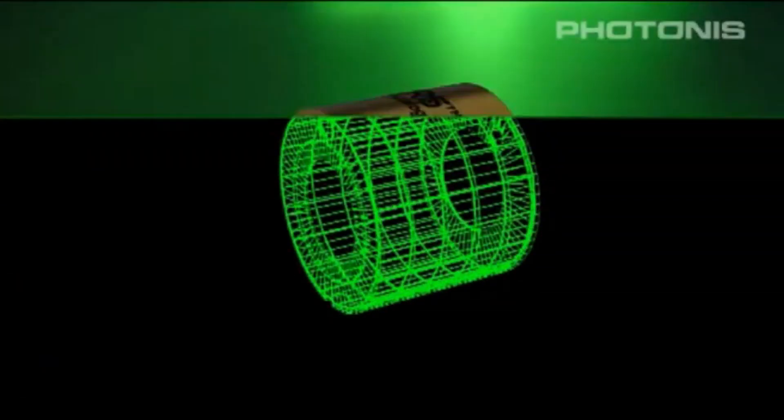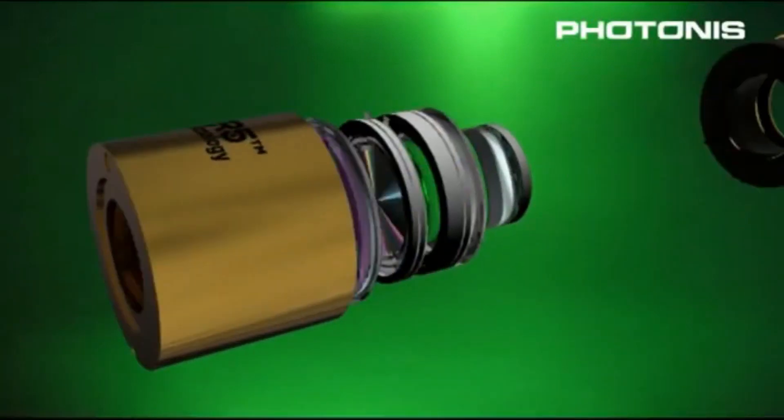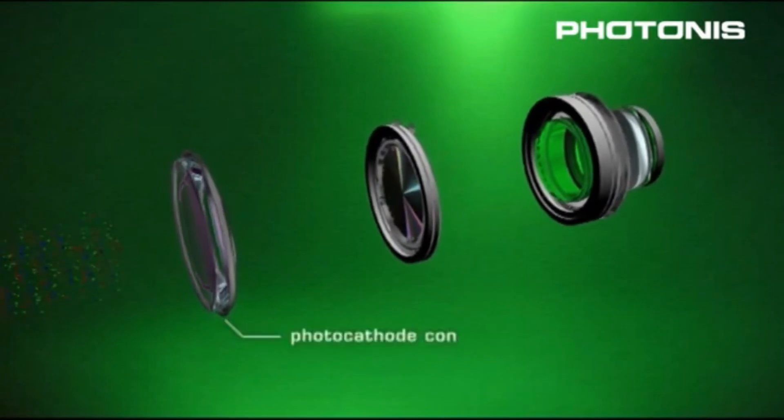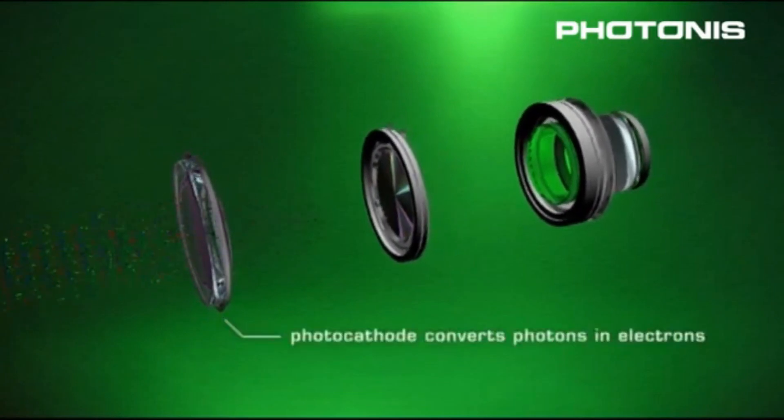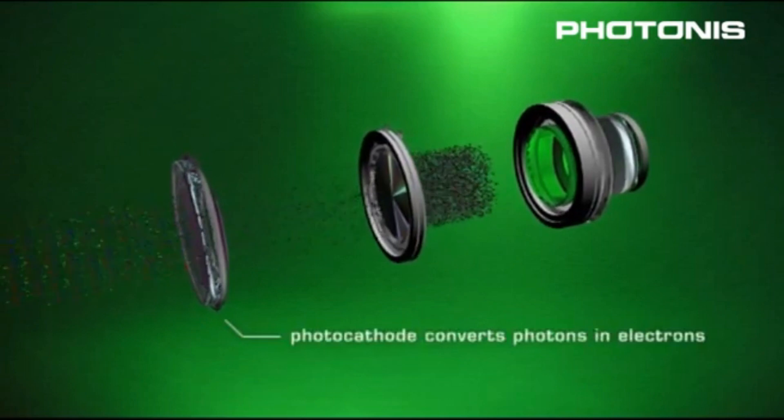Let's look into image intensifiers in cath lab. Image intensifier tubes, or IITs, are optoelectronic devices that allow many medical imaging devices to function. They convert low levels of light from various wavelengths into visible quantities of light at a single wavelength.